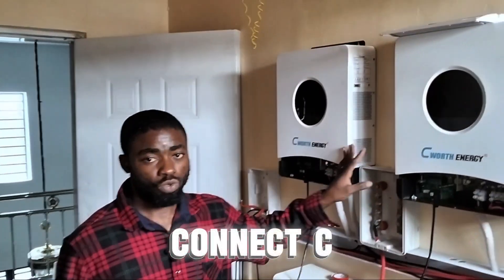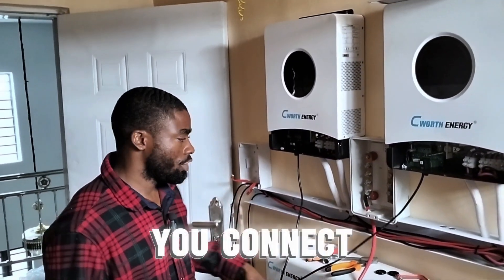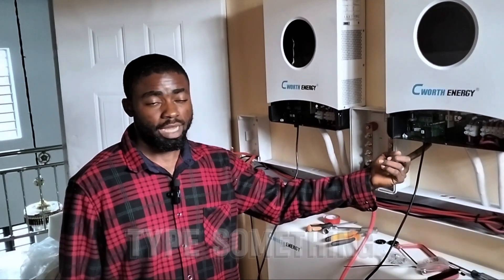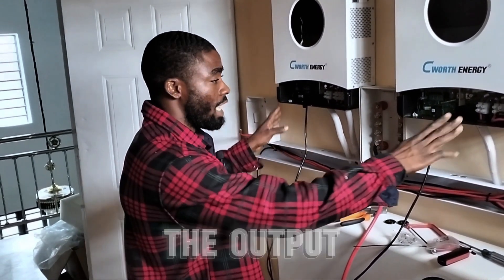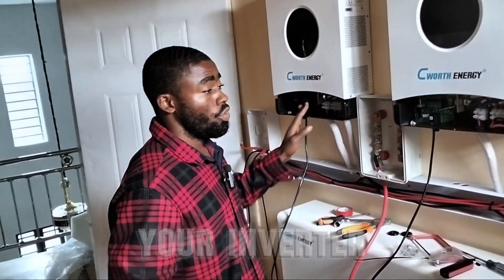That is how to connect Cworth inverters in parallel. Always make sure you connect your communication cable between the two, and also connect this USB-type connector. Don't forget to loop the output and loop the input together. If you don't loop the output of this inverter to the output of the other, your inverters will not communicate and will show an error.